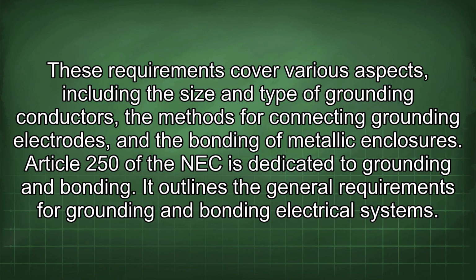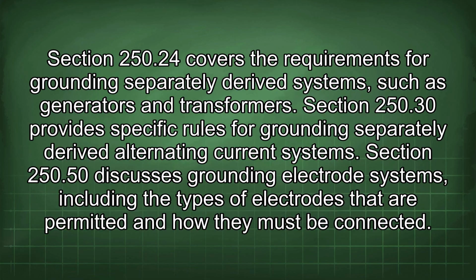Article 250 of the NEC is dedicated to grounding and bonding. It outlines the general requirements for grounding and bonding electrical systems. Section 250.24 covers the requirements for grounding separately derived systems such as generators and transformers. Section 250.30 provides specific rules for grounding separately derived alternating current systems. Section 250.50 discusses grounding electrode systems, including the types of electrodes that are permitted and how they must be connected.